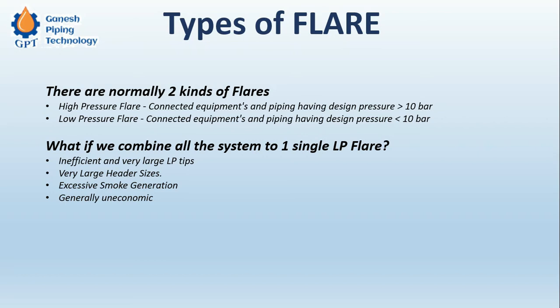There are normally two kinds of flare systems: high pressure flare and low pressure flare. The high pressure flare is connected to equipment and piping having a design pressure greater than 10 bar, while the low pressure flare is connected to equipment and piping with a design pressure less than 10 bar. That is the main difference between them.